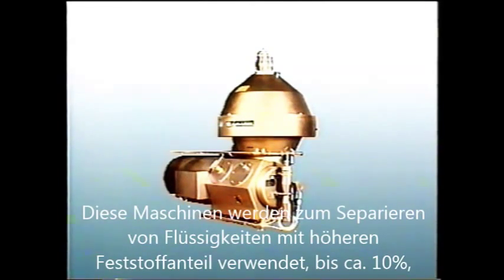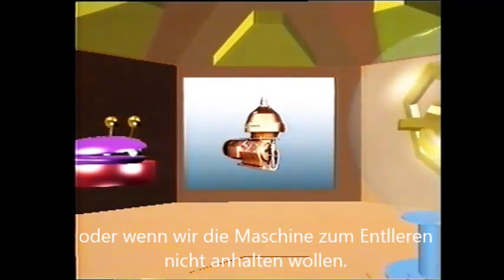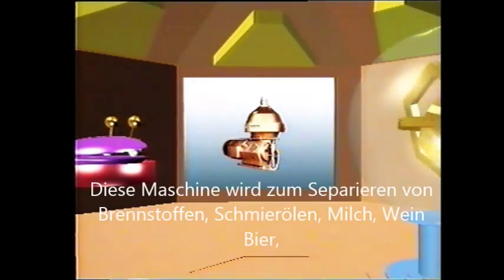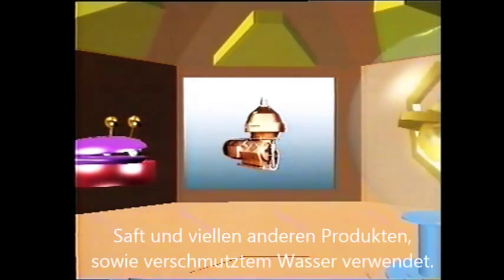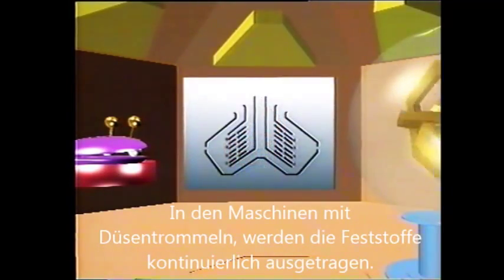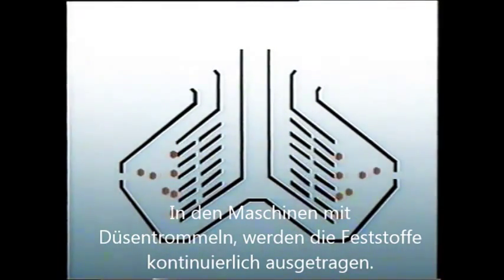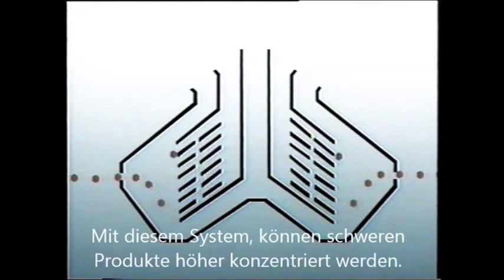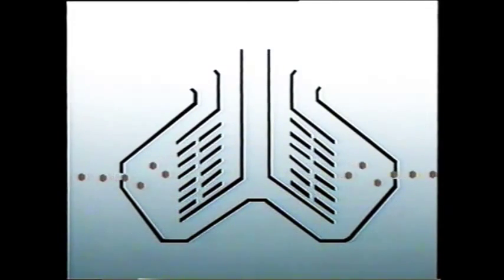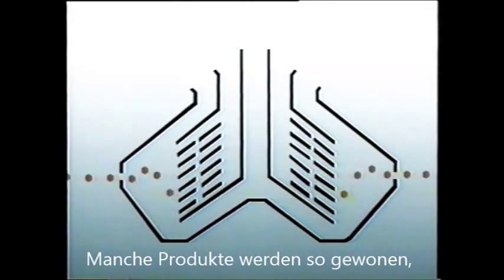PX separators are used for liquids with a higher solids content — up to 10% — or when we don't want to stop the machine for emptying. They are used for fuel and lubricating oils, milk, wine or beer, fruit juice, and radioactive waste water. In the nozzle separator, the solids escape continuously through the nozzles around the bowl periphery. With this system, the solids may be recycled for further concentration. In some cases, the solid itself is being recovered and the liquid is the byproduct.